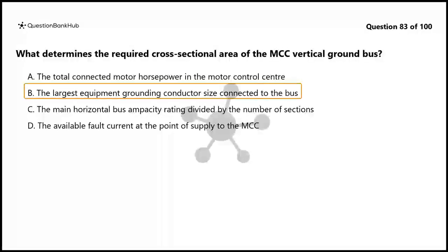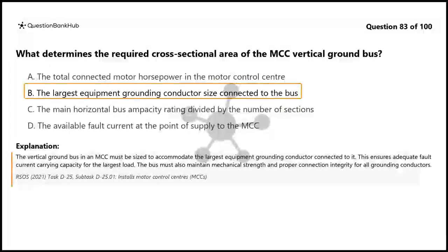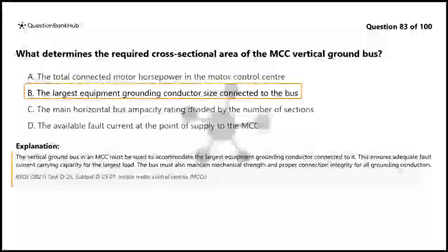The correct answer is B. The largest equipment grounding conductor size connected to the bus. The vertical ground bus in an MCC must be sized to accommodate the largest equipment grounding conductor connected to it. This ensures adequate fault current carrying capacity for the largest load. The bus must also maintain mechanical strength and proper connection integrity for all grounding conductors.